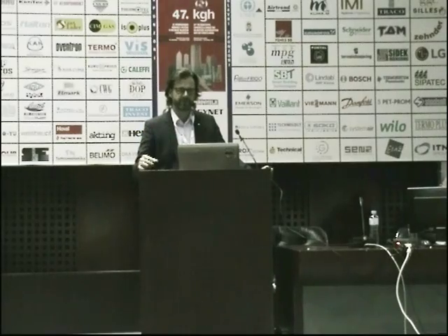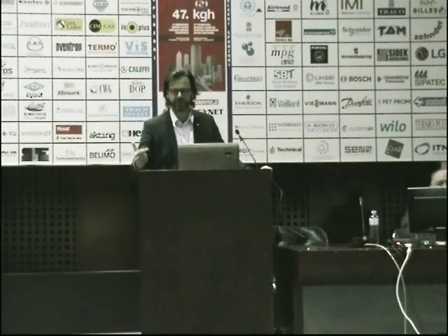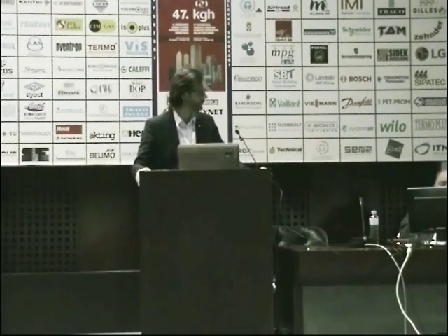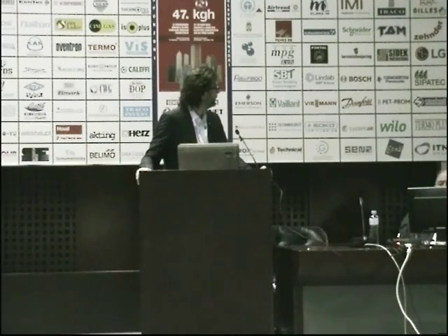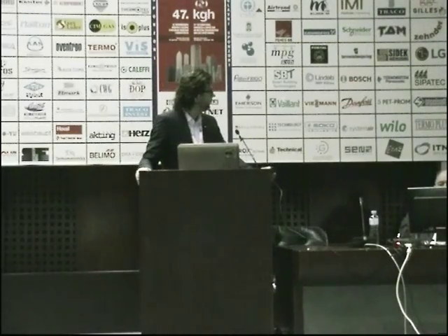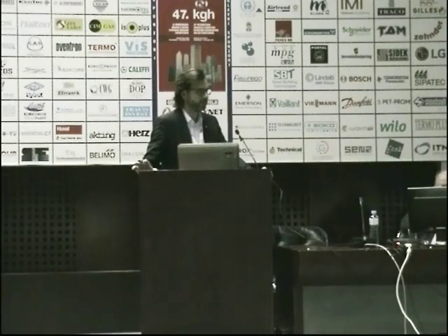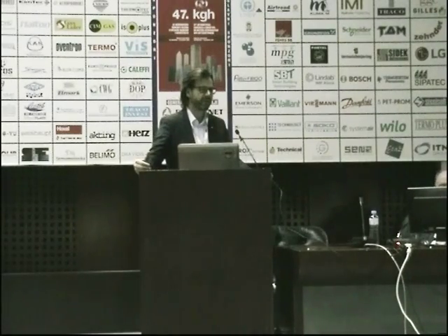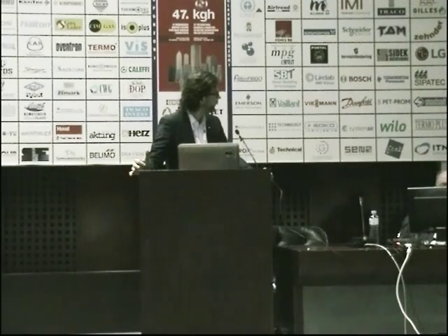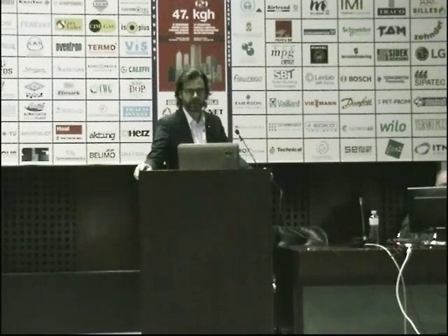The old documentations on the sites were 3 pages: the company name, the refrigerant, and the emergency number where you phone when something happens. The projects are now fully documented. We set up a service and maintenance system where we define, when there is an alarm, how many hours they have to come and what service things they have to do. We also set up a monitoring system on energy consumption and on temperature alarms.